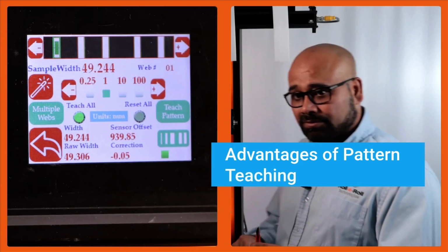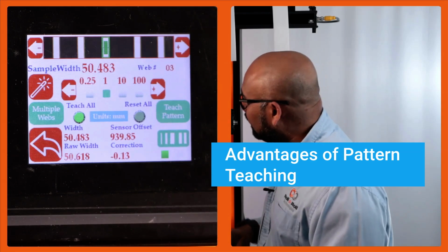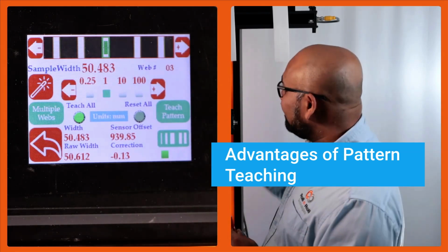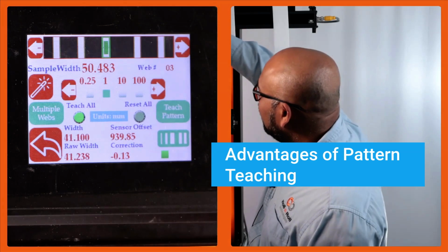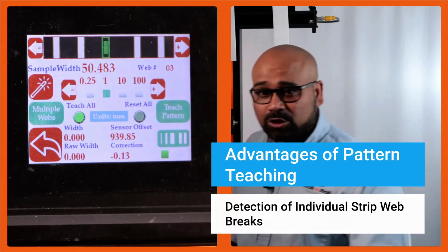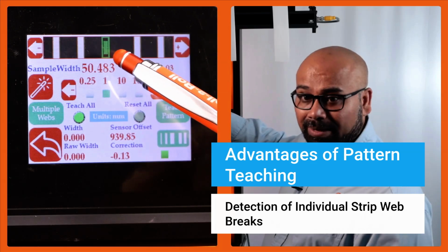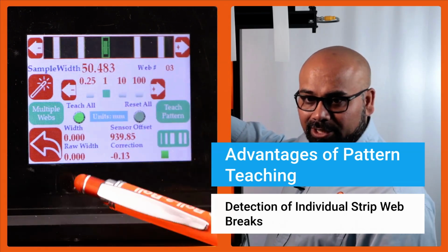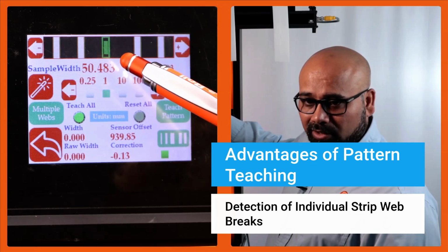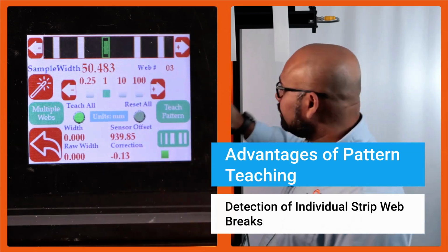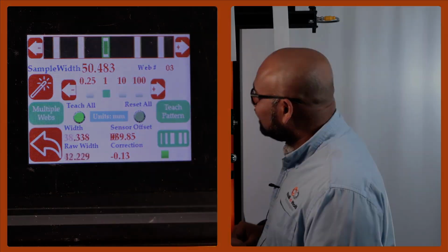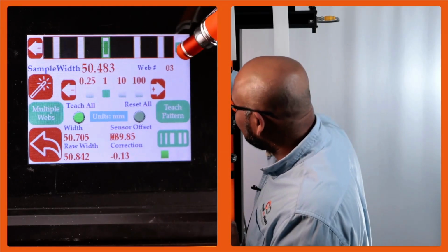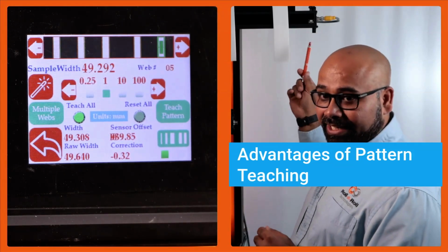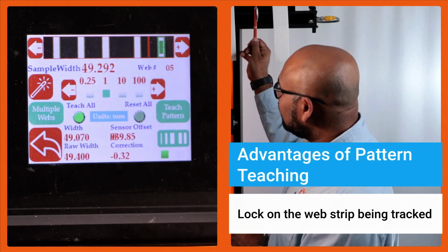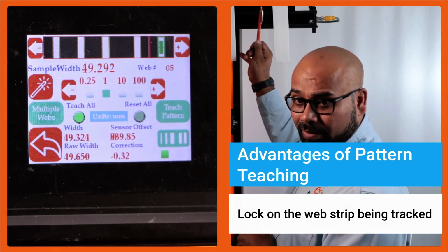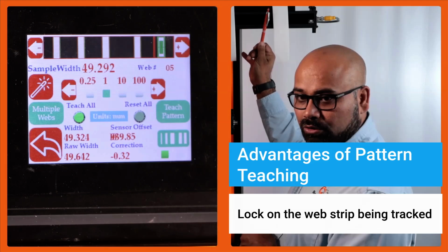What is the advantage of that? If I have, let's say I'm in Web 3, right? And if the Web 3 breaks right now, it is actually showing you that, hey, I'm supposed to see a web there. It's broken. The value is 0, and it's going to provide an alarm or alert right there. That's one advantage of that. Another advantage with that is that, let's say I have a Web 5 that I'm tracking right here, and if I have another material that comes in between there, the Web 5's measurement is not affected by that whatsoever.